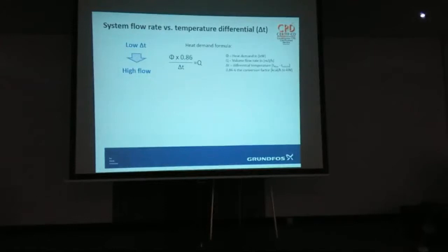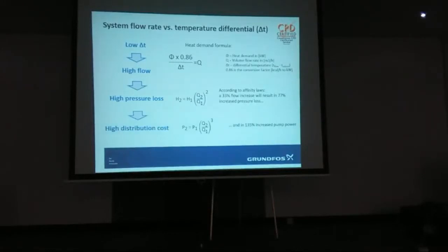So, low differential temperature equals high flow, high pressure losses, and high distribution costs. Which, in theory, if we increase the flow by 33%, gives a 77% increase in pressure, and a 135% increase in power required. So, narrow the band, bigger motors to push on, and you've got less control.